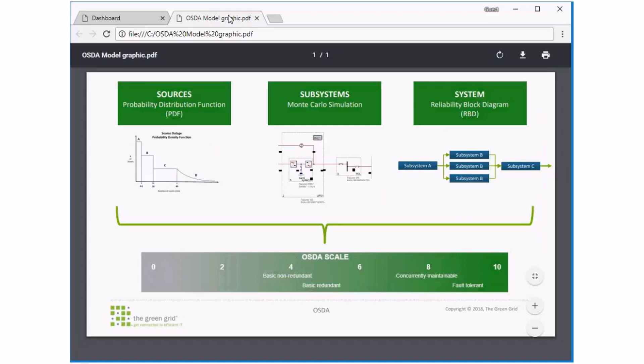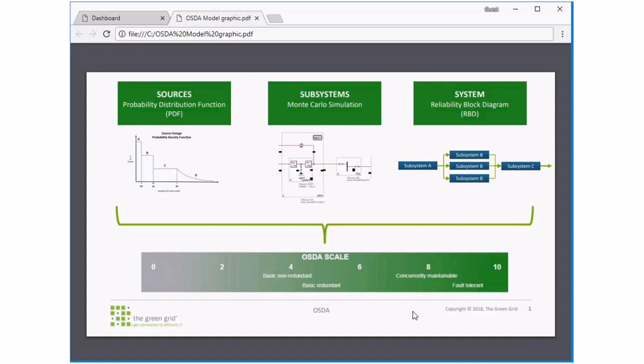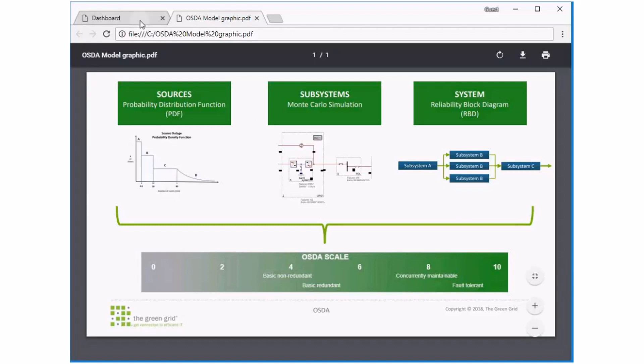All of this gets translated into an OSDA scale which goes from 0 to 10. This allows you to compare and contrast different design architectures and different sources against each other in a relative fashion. The whole purpose of OSDA is to look at alternative designs and alternative energy sources and see how they stack up against traditional sources, to encourage new ways to design data centers. This happens very early in the business cycle, in an exploratory phase before the design phase.